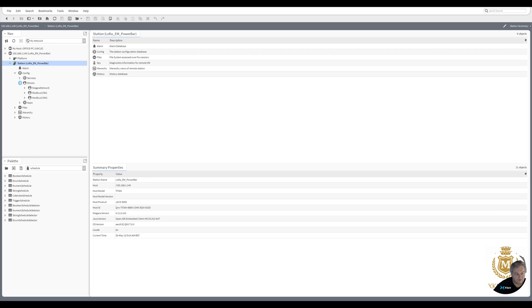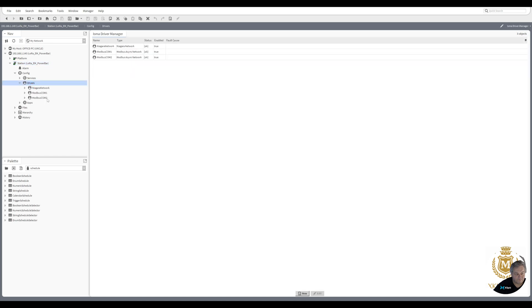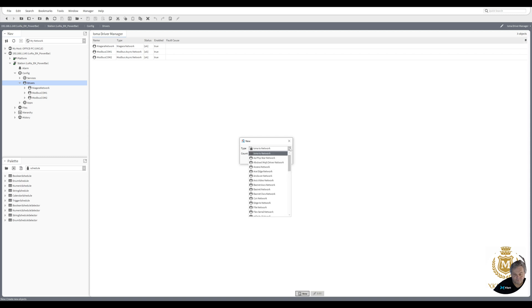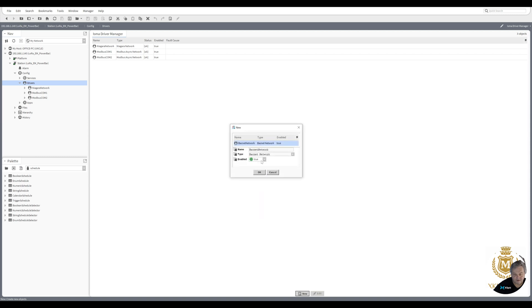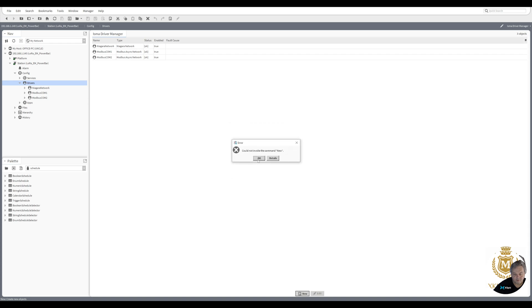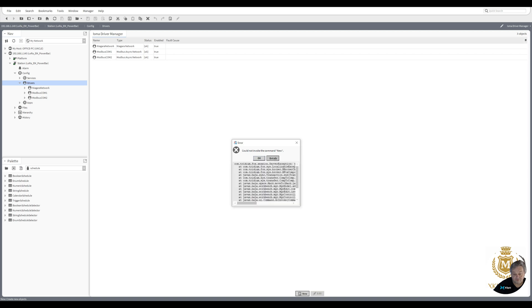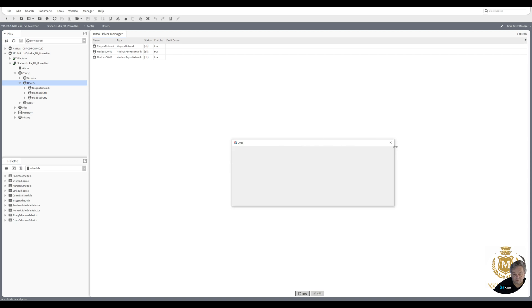So that's now rebooting. Our station's rebooted. Now we don't have BACnet on this station. Now let's log it back into this station again. I'm going to go back to drivers and we're going to install a BACnet driver. Could not invoke the new command. That's because the driver is not loaded on the station and you will see missing module BACnet.